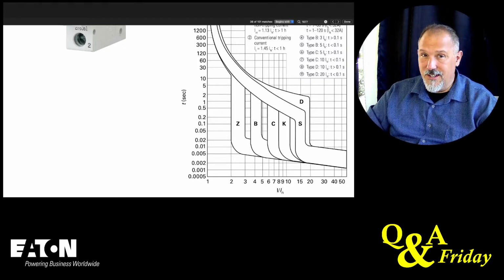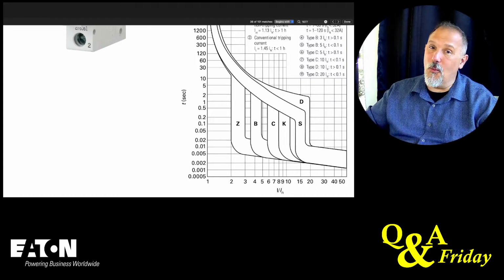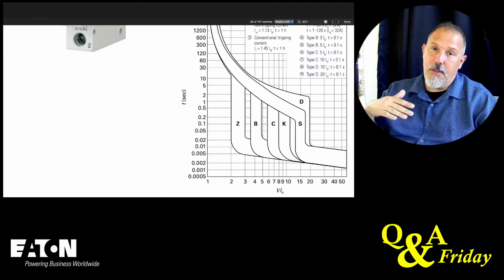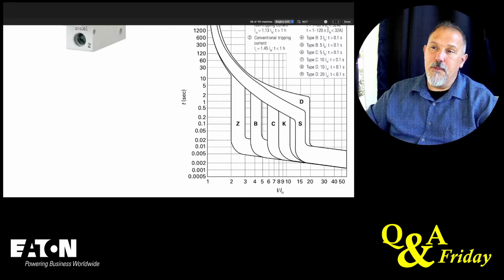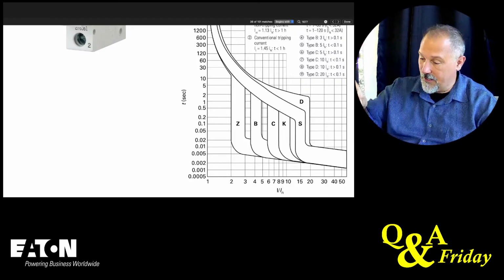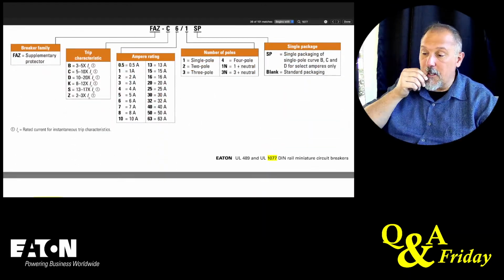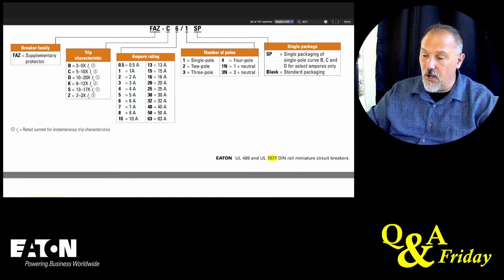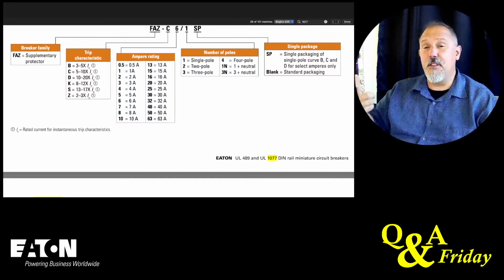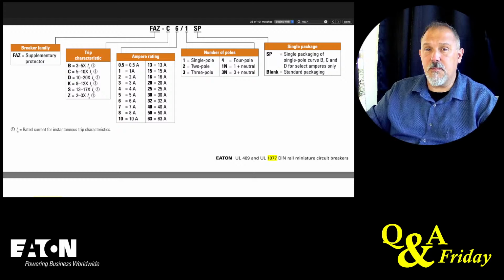0.0005 seconds. Now, a lot of people have a misconception to think that all trip curves start at 0.01 seconds because that's where they see most TCC curves. In reality, manufacturers do provide data below that 0.01 second line. We just elect to ignore it in many cases for a lot of different reasons, which I'm not going to get into. All right, and look at the ampere ratings, down to 0.5 amps, all the way up to 63 amps for this specific manufacturer, for this specific catalog number.